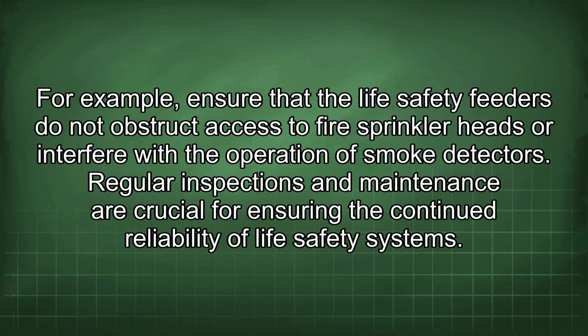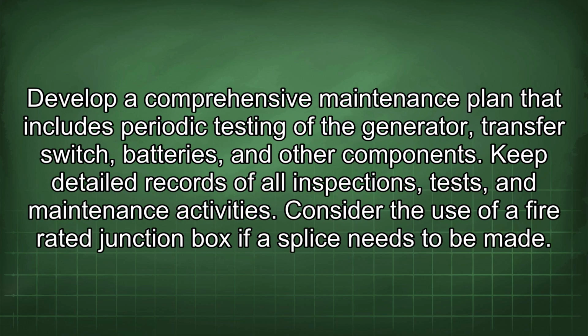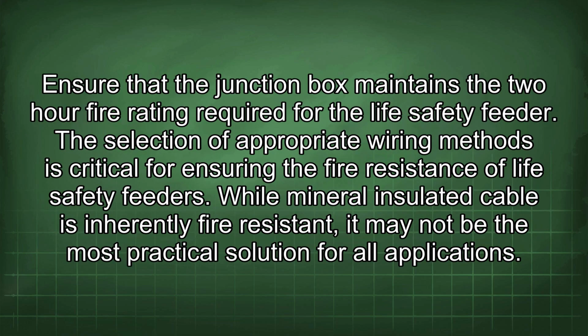Regular inspections and maintenance are crucial for ensuring the continued reliability of life safety systems. Develop a comprehensive maintenance plan that includes periodic testing of the generator, transfer switch, batteries, and other components. Keep detailed records of all inspections, tests, and maintenance activities. Consider the use of a fire-rated junction box if a splice needs to be made. Ensure that the junction box maintains the 2-hour fire rating required for the life safety feeder.